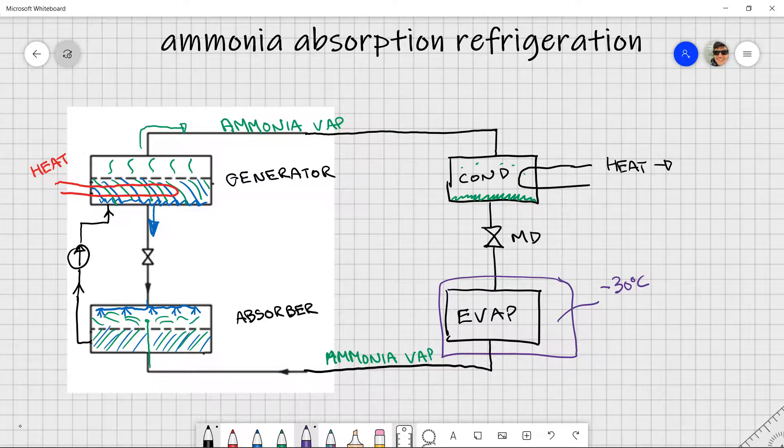So we have sort of this circulation of water and when it's down at the bottom in the absorber it's absorbing ammonia vapor and becoming a more concentrated ammonia mixture, and then it's pumping it up to the top where we drive off some of the ammonia by adding heat and that creates a weaker water mixture.